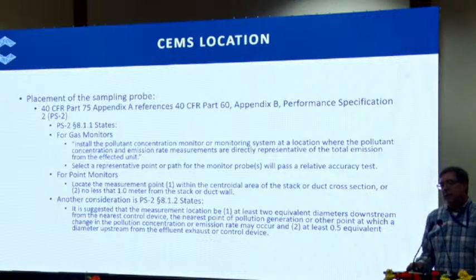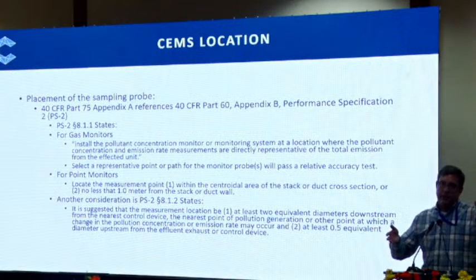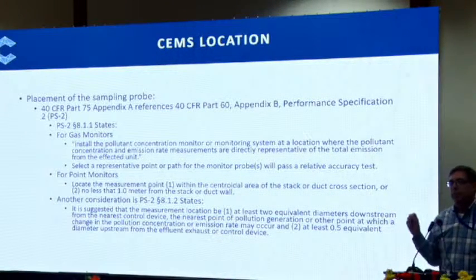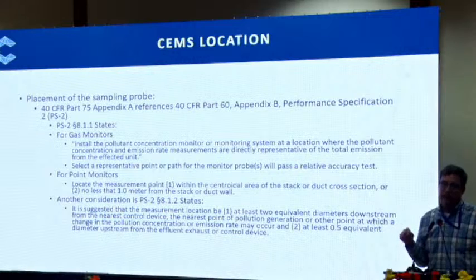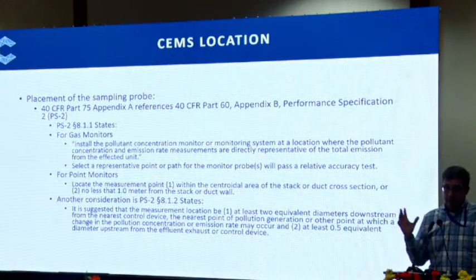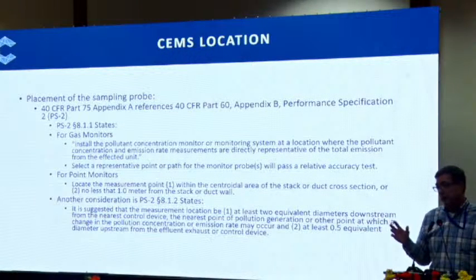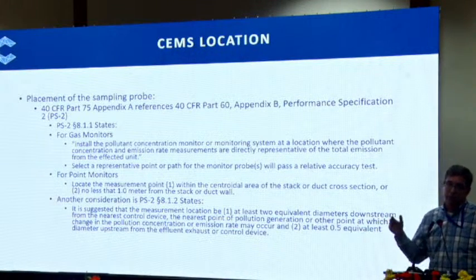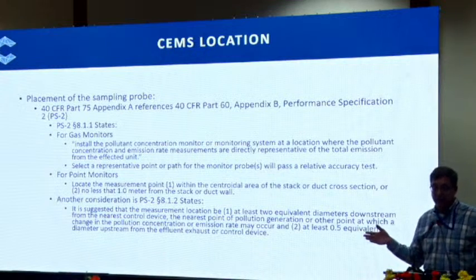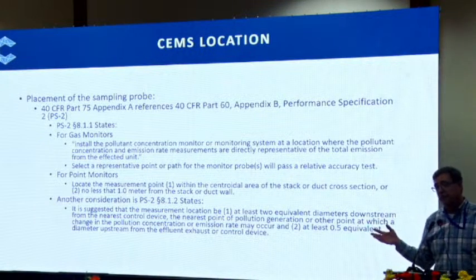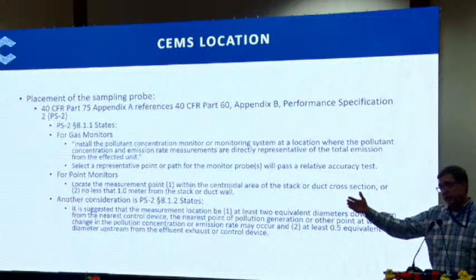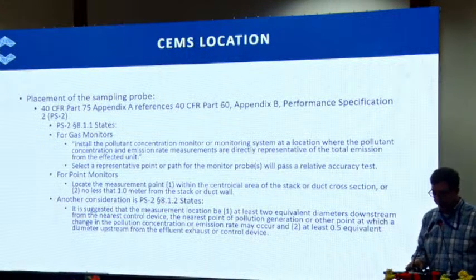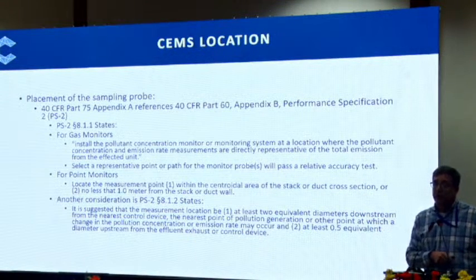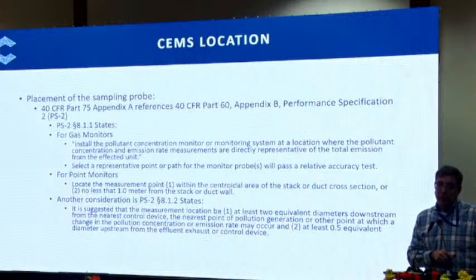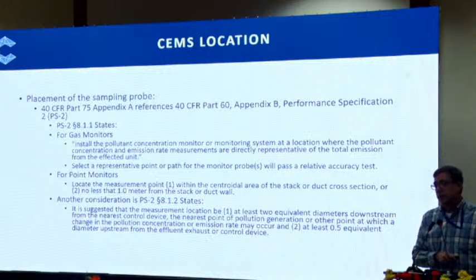So this gives you a little bit of a buffer between where you have a transition in a duct. In this case, EPA Method 1 would have you go from the nearest disturbance, which is a transition or a turn or some change in the duct dimension. But this is allowing for you to go from the actual exhaust of, say, your FGD, which is a little bit different. So you can be closer to the FGD exhaust than you would maybe on a stack, right? So if you had a ductwork location that may be reasonable and be able to provide you with a representative location, then you could use that.